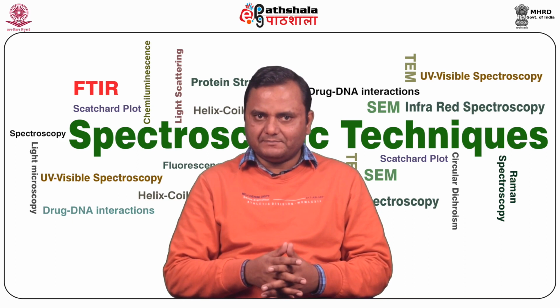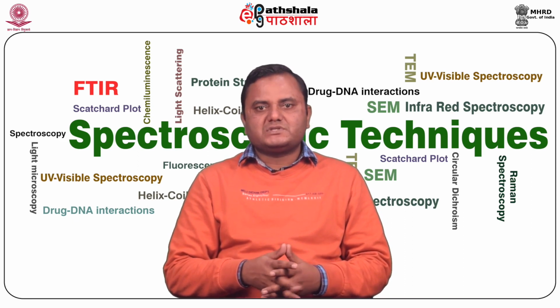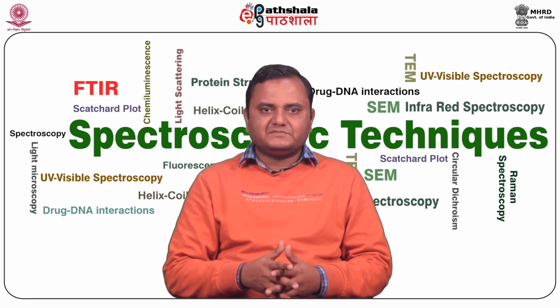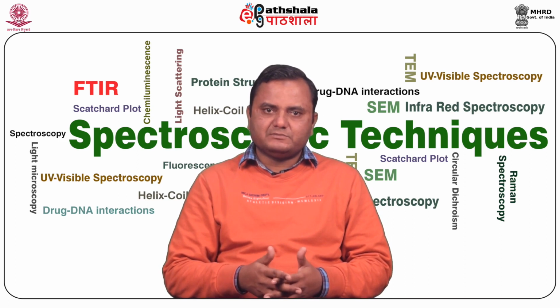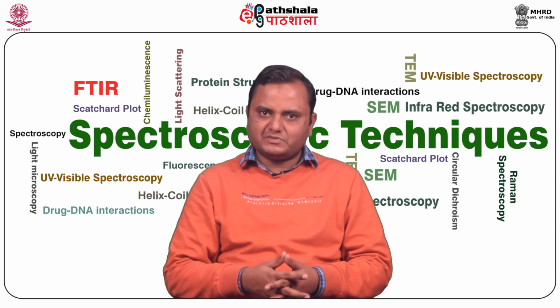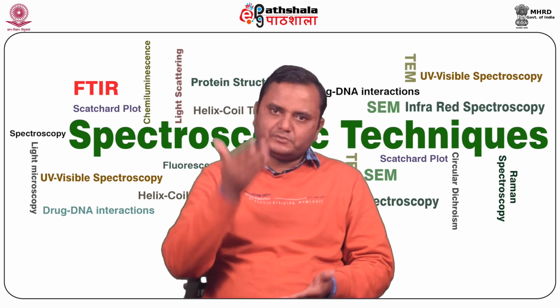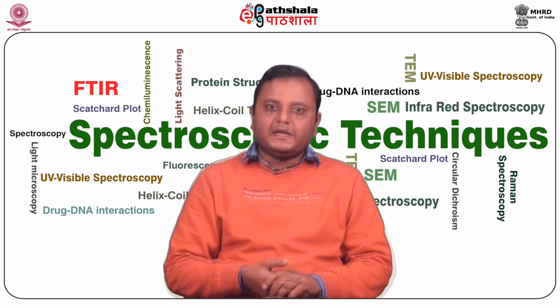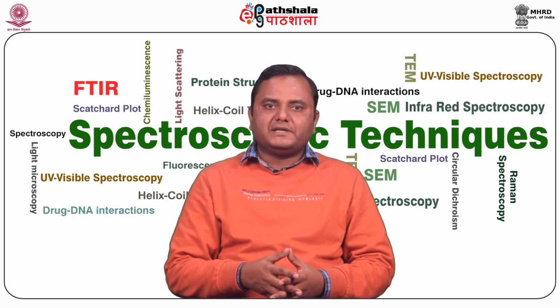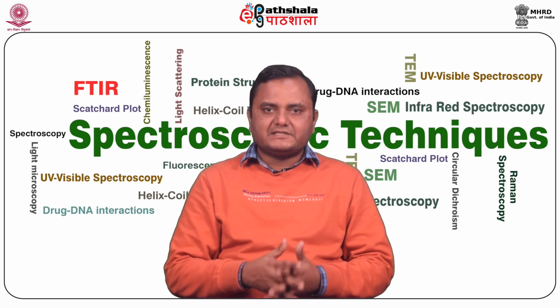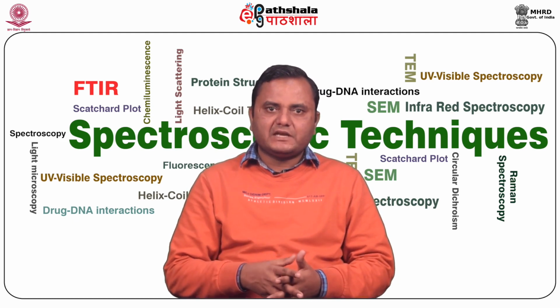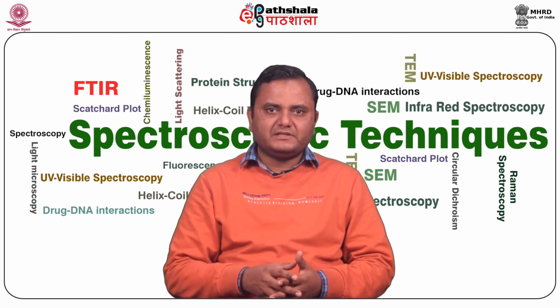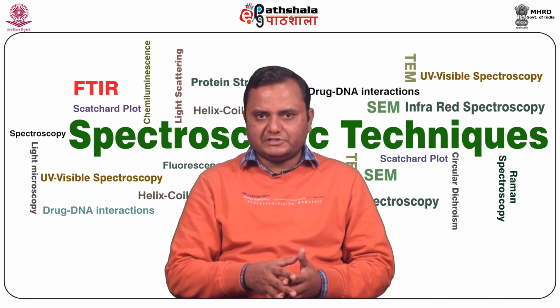The lamp source used is a xenon arc lamp that emits radiation in the UV, visible and near IR region, which has a sufficient amount of energy to excite the electron from its ground state to the excited state. And the light is directed by an optical system through the excitation monochromator, which allows either pre-selection of wavelength or scanning of a certain wavelength range.